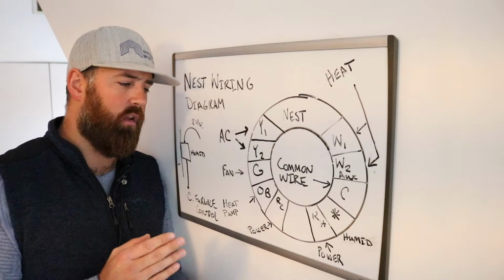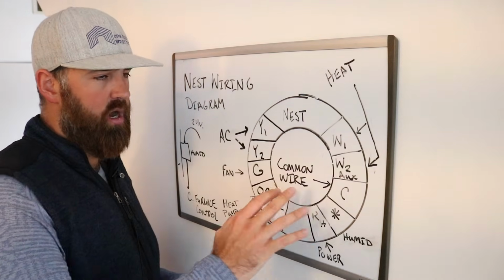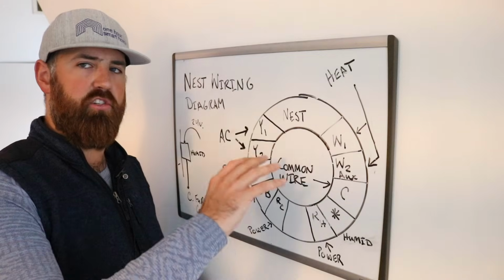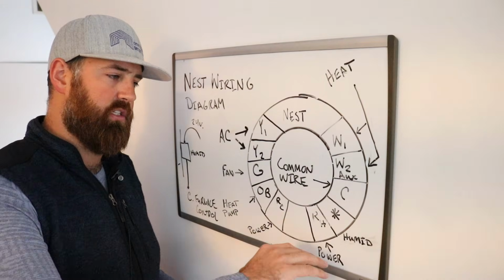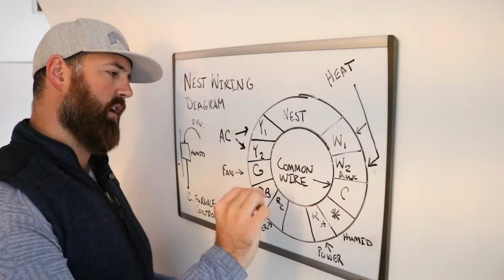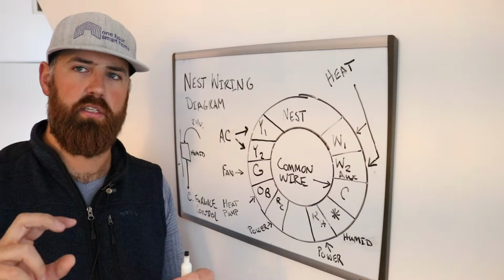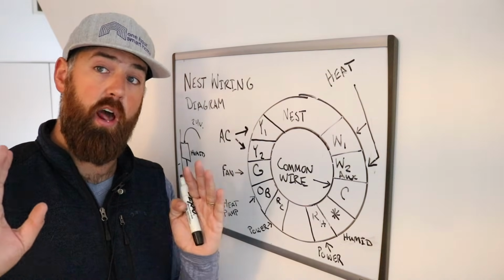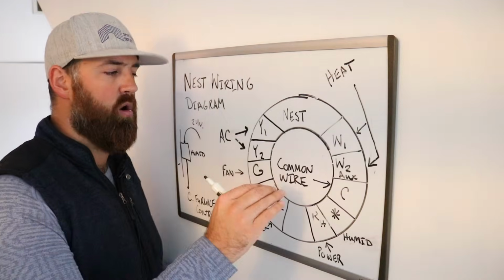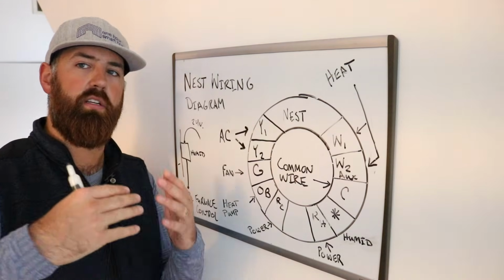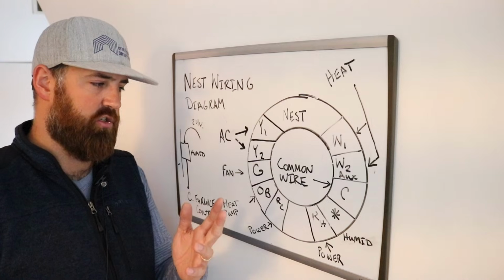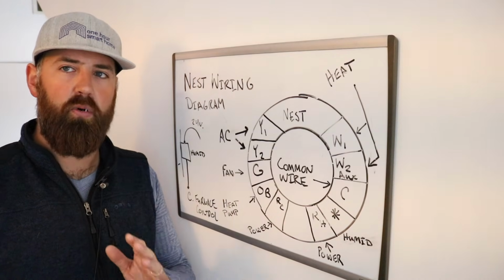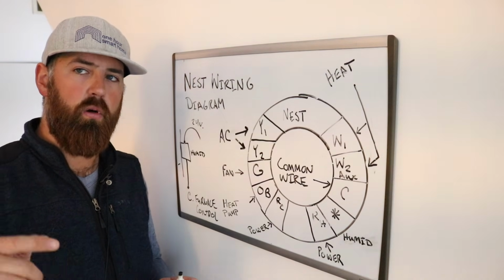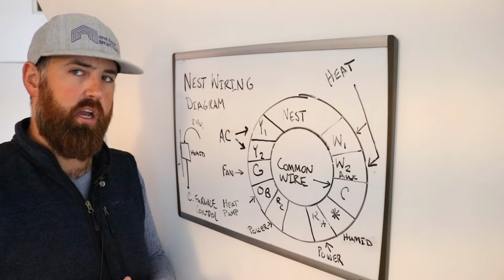A common wire allows power to constantly circulate through the Nest, charging the battery so you get good performance, without going through the air conditioner terminal and potentially causing short cycling, or not providing enough power because of how throttled it needs to be so it doesn't turn on your AC. So not everybody needs a common wire, but some of you do, and that's why we created a common wire tutorial.